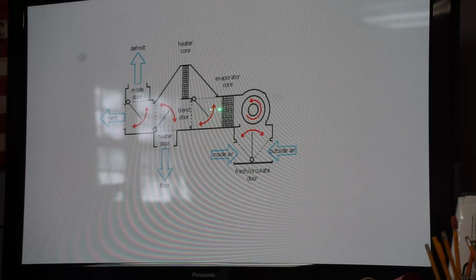If we've got 55 or 50 degree dehumidified air coming off that evaporator, and we start blending that door back open towards hot, even though it's a 75 degree day in the summer, man, that car's comfortable. We're doing sensible reheat with that coil that's always active, unless, nowadays you got some relays that lock it out. And we're getting closer to that neutral 70 degree air. So this becomes a DOAS unit, and I see you guys do some VRF. If there's DOAS units associated with that, we can't always be dumping 55 degree air in the space because we'll overcool. Reheat is key there.